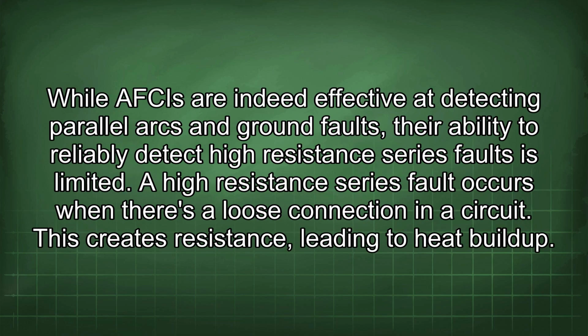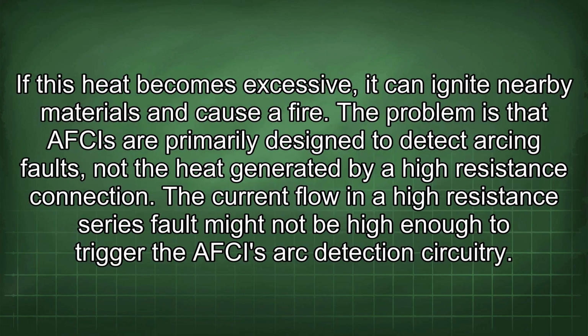While AFCIs are indeed effective at detecting parallel arcs and ground faults, their ability to reliably detect high-resistance series faults is limited. A high-resistance series fault occurs when there's a loose connection in a circuit. This creates resistance leading to heat buildup. If this heat becomes excessive, it can ignite nearby materials and cause a fire.